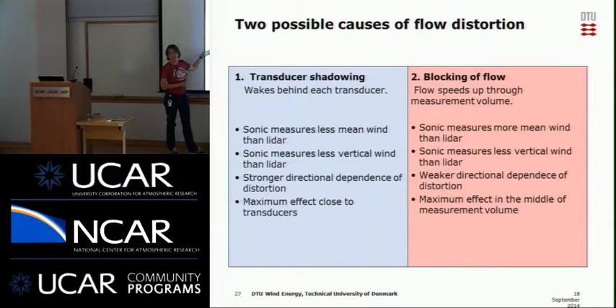If we have transducer shadowing, we would expect a stronger directional dependence of the distortion as compared to the blocking, where we would see a weaker dependence. This is just what we pictured in our mind. And with transducer shadowing, of course, the effects are strong very close to the transducers, whereas we measure in the middle of the sonic volume. But if we have the blocking of the flow, it would have the maximum effect in the middle.